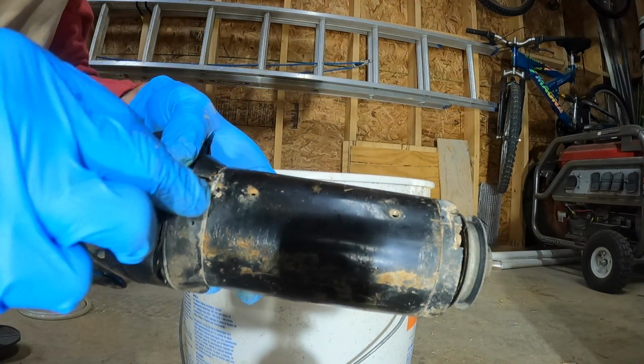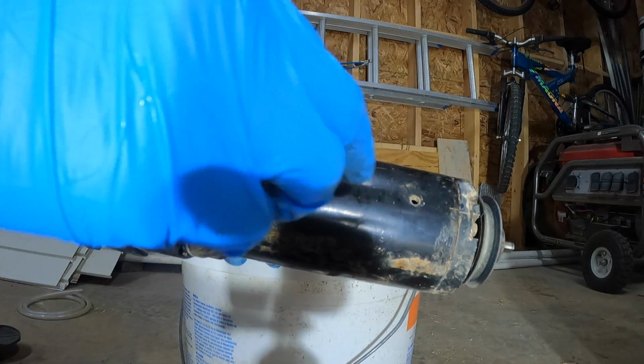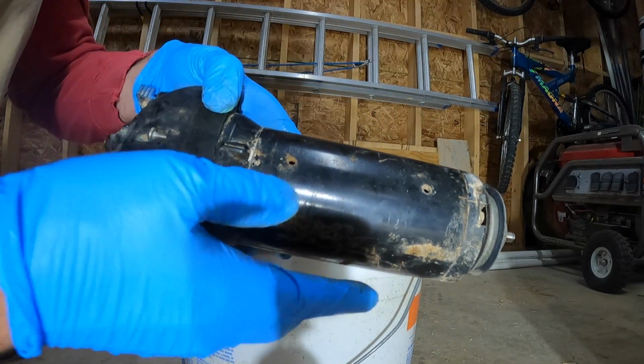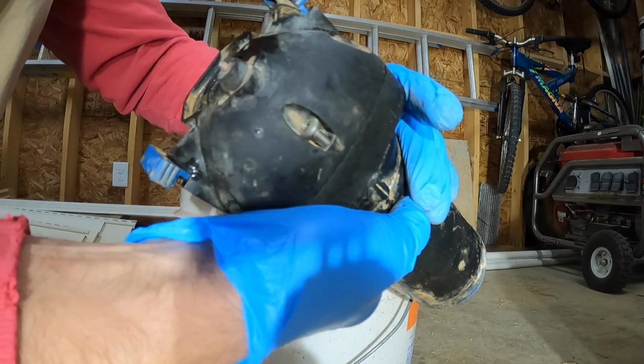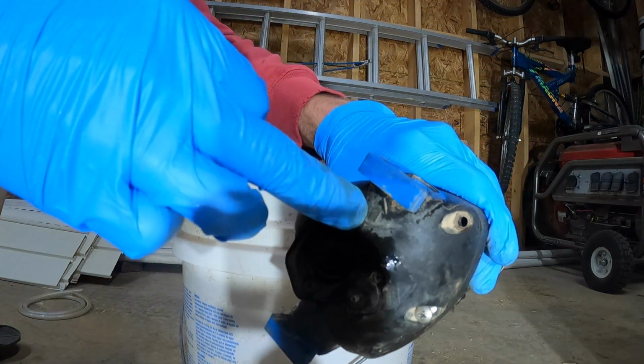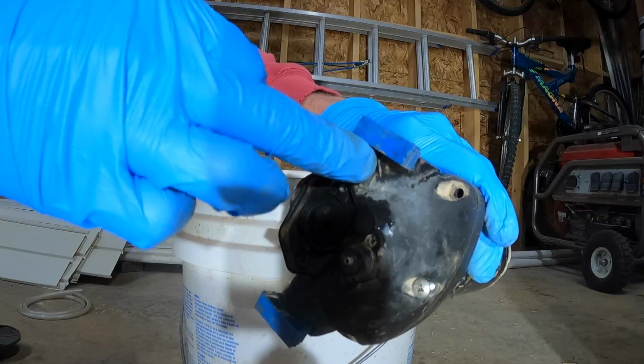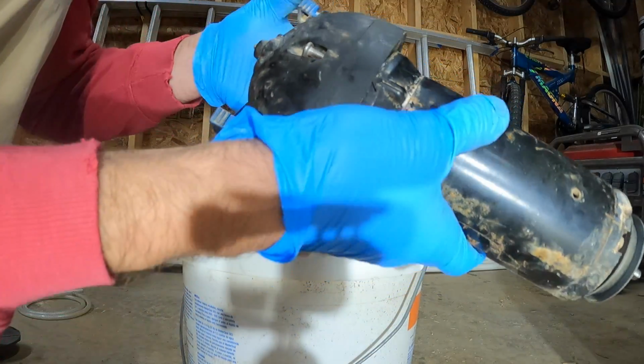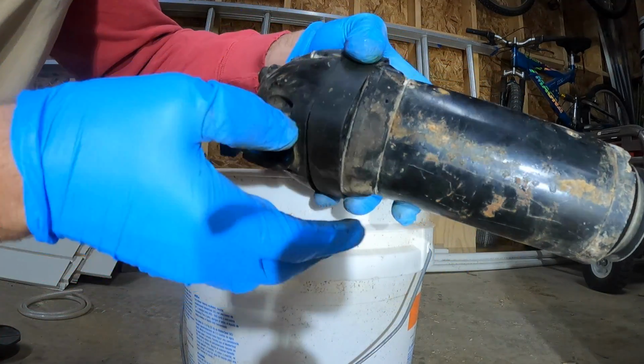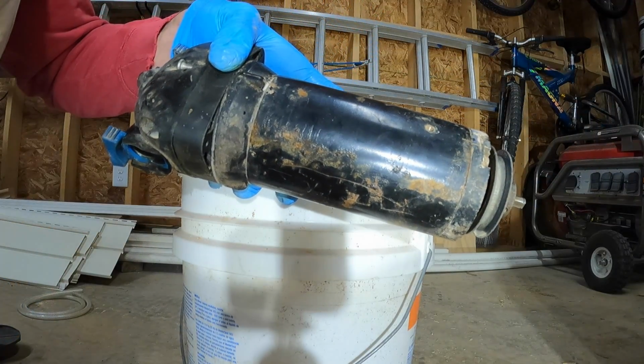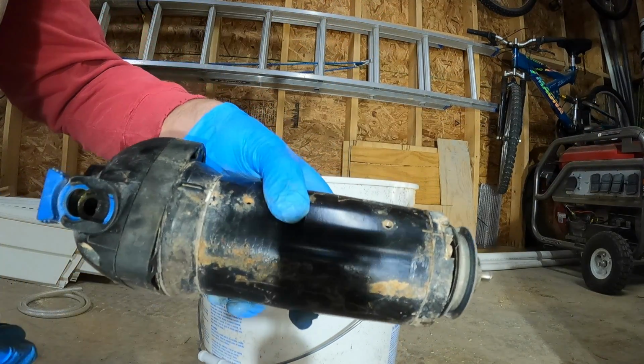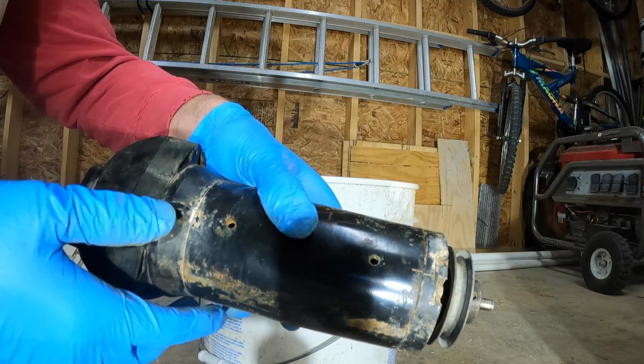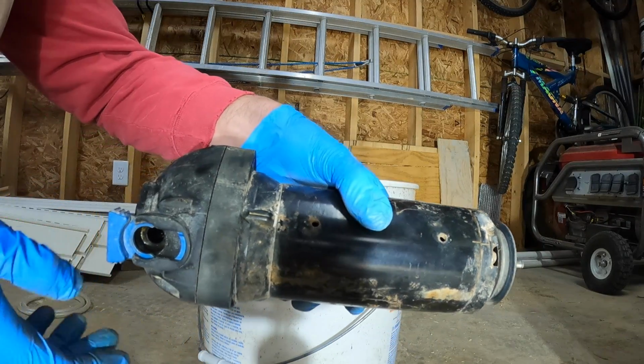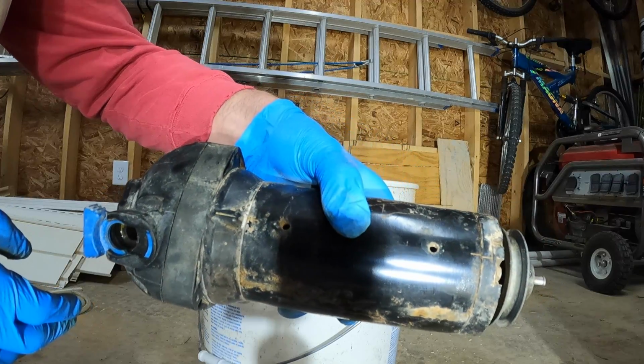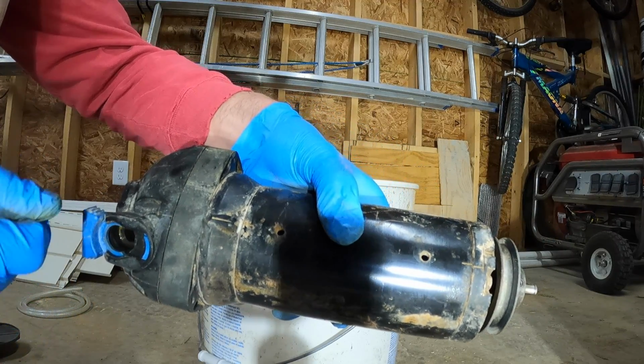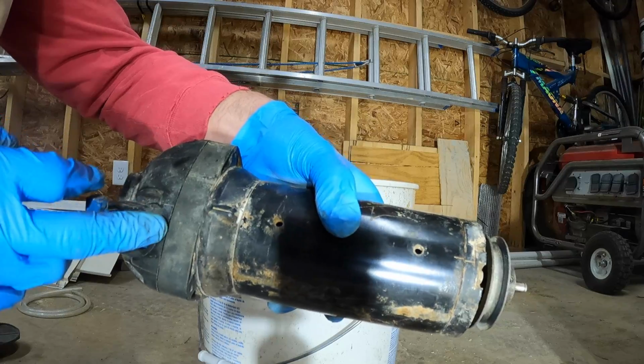So when I pulled it off my machine, it was mounted just like this with the screw holes towards the top. And on the upper side was the outlet, and you can see I've got an arrow here, and that points to the discharge side or the outlet. And then underside was the inlet, and that's how it was mounted, so that's how it goes back on oriented. So I believe I'm actually going to orient mine different than what it was when I pulled it out. I'm going to orient it to where the suction side is going to be closer to the tank, and the discharge side is going to be where the suction side was.